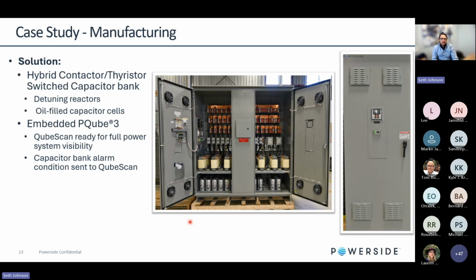So we developed a solution that would allow us to correct for those dynamic points during the pressing cycle. This is a hybrid solution with our PowerBar series product line, where we're doing both contactor and thyristor switching. Over here on the left, we've got contactor switched stages. This is 800 kVAR of contactor switched capacity, and it's going to take care of the base load of the facility. Even when they're not doing the pressing cycle, there's still a very high base load, which needs reactive power compensation.